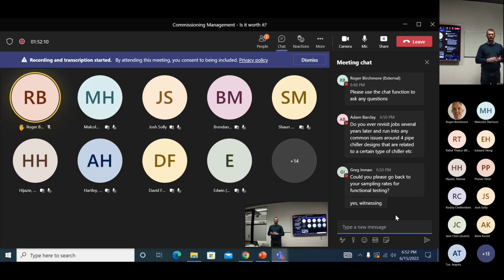For mission critical or life safety systems, I tend to look at 100% of those. For fire alarm systems, often the contractor says we only need to look at 20%. I say, actually, you need to test 100% of your system. Every year you test a different 20%, so over 5 years you've tested the whole system again, but it has to be fully tested at handover. They say no, we only need to test 20%.